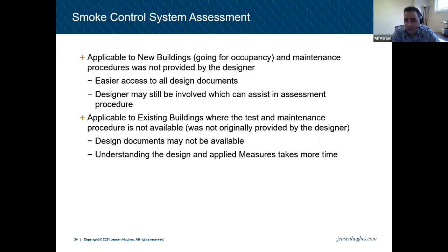The other one is existing buildings, where the test and maintenance procedure is not available. That's 99.9% of the existing buildings. Honestly, I haven't seen anyone. I just put that 0.1% for, I don't know, maybe some buildings, but I haven't seen that. So none of the existing buildings have that procedure, and nobody's following any maintenance procedure for these systems in existing buildings. And the challenge here is that the design documents may not be available. We're dealing with a 30-year-old building. Who knows where the mechanical design document is? So it's really hard to assess these buildings. Understanding the design and the design approach that was taken 30 years ago, and the measures taken, is not impossible. We get it done, but it's a little bit time consuming. Compared with a new building, obviously, it's much more work.